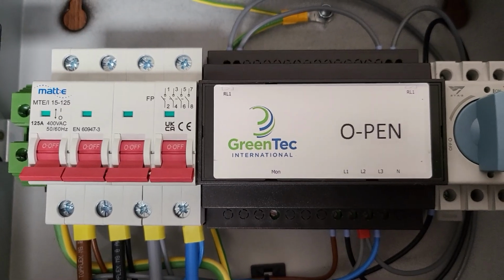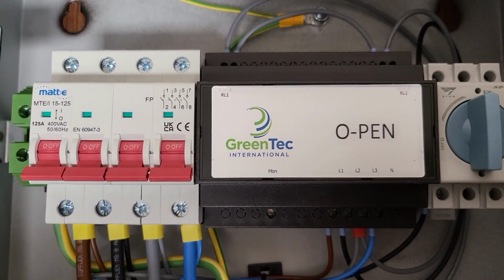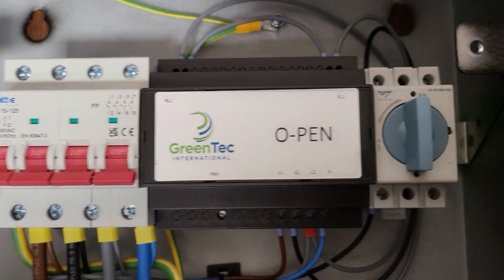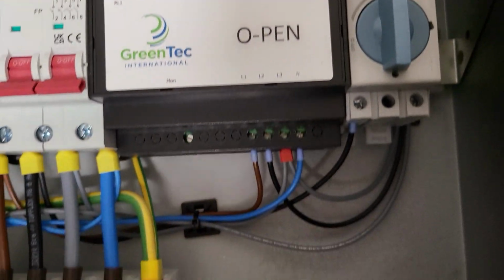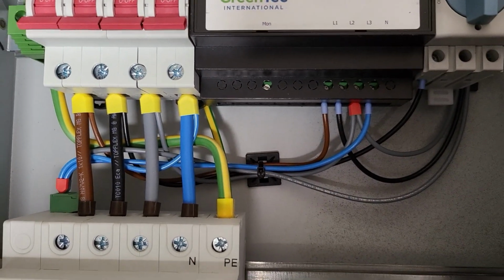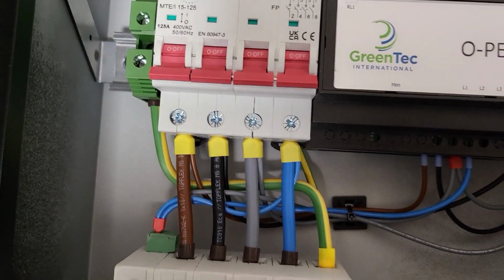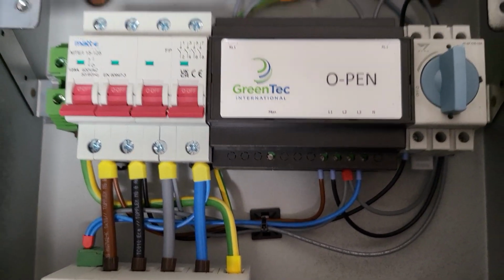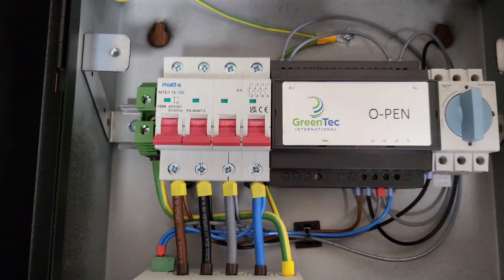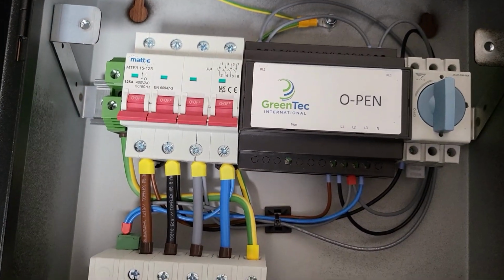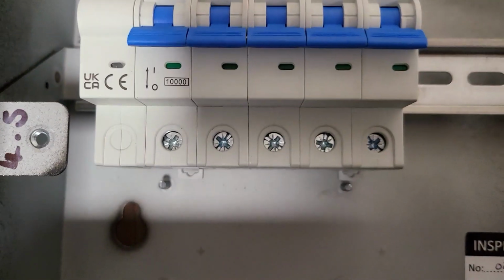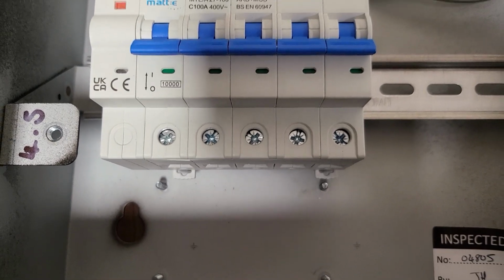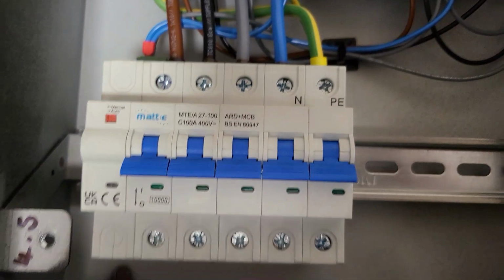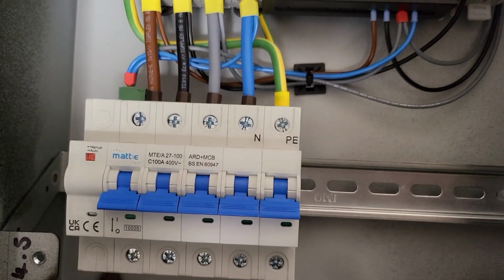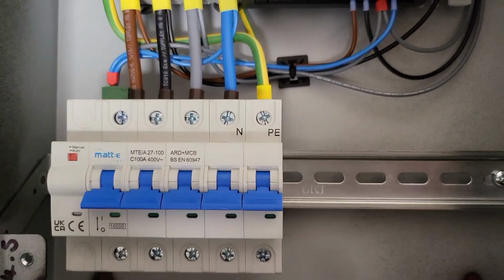There's then this GreenTec International Open detection, and a little test trigger here that you can see is wired into that and also into the L1. So that's going to simulate a loss of a phase to operate the test feature. I'll speak about that as we go through the manual. And then down here, you've got your connection for all of your outgoing cabling off to the charge point itself, and you can see that's for your L1, L2, L3, neutral, and your earth.